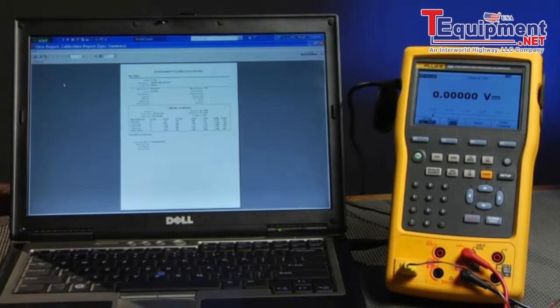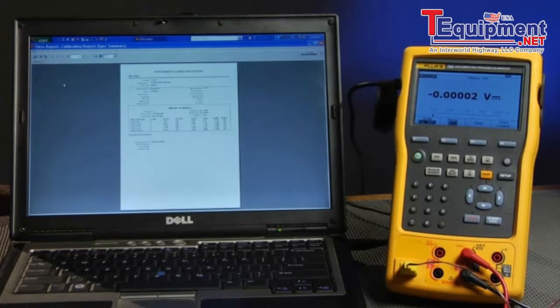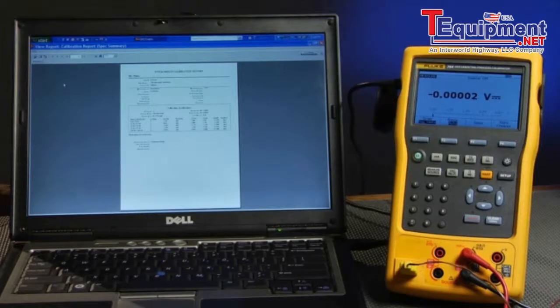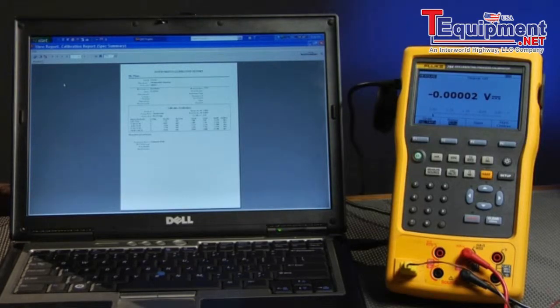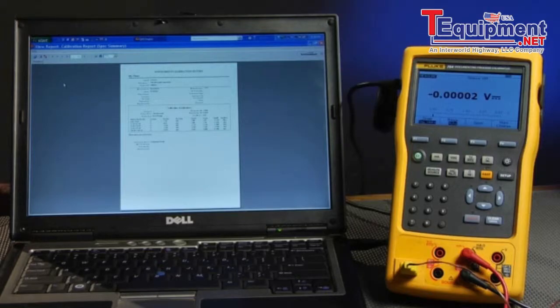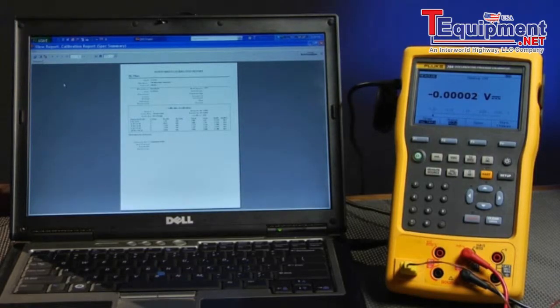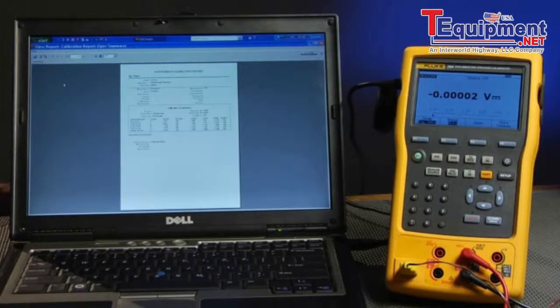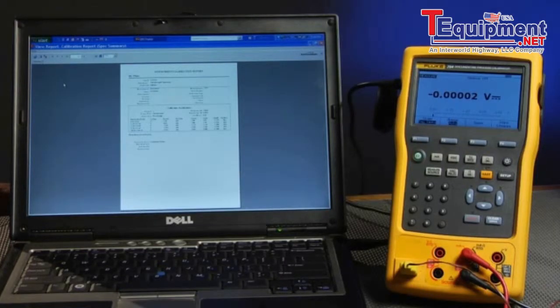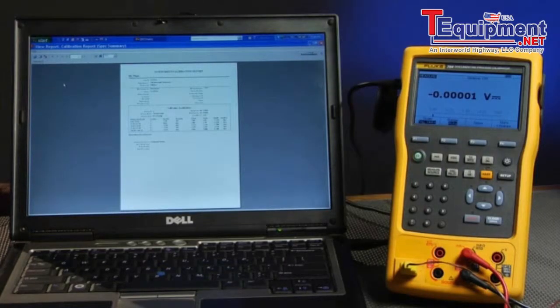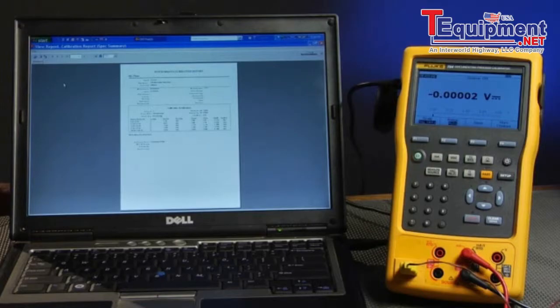We've gone full circle. We've created a tag in DPC track 2 software, loaded into the Fluke 754 documenting process calibrator, documented the results of the transmitter using a tag that was downloaded, uploaded the results back to DPC track 2 software, reviewed the results, and printed a report.